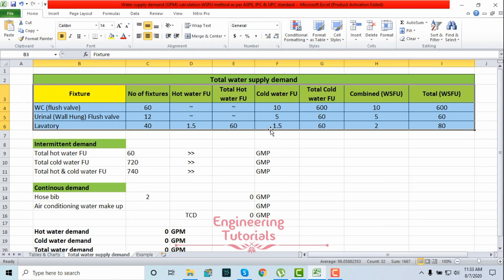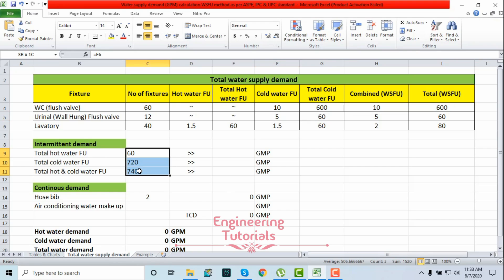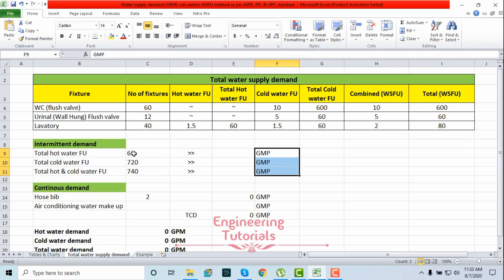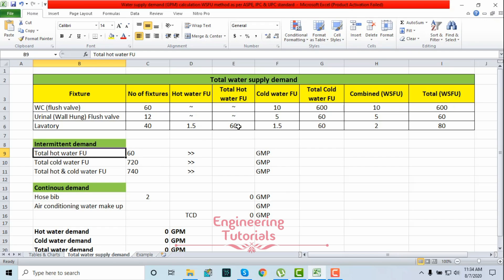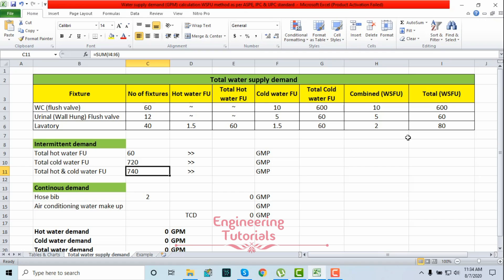The demand we've calculated so far is the intermittent demand — that is, non-continuous demand. It is not used all the time; its frequency of use varies. We need to add continuous demand to the non-continuous demand if any continuous demand is available. But before that we need to convert our fixture unit values into GPM. Total hot water fixture units = 60, total cold water fixture units = 720 (the sum of all three fixtures), and combined water supply fixture units = 740.